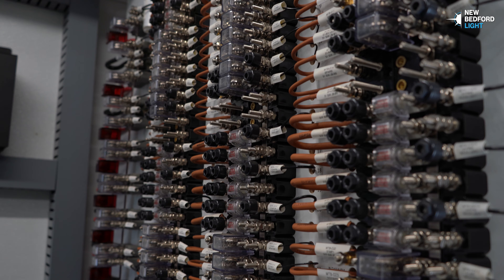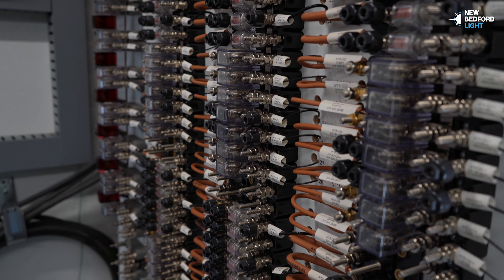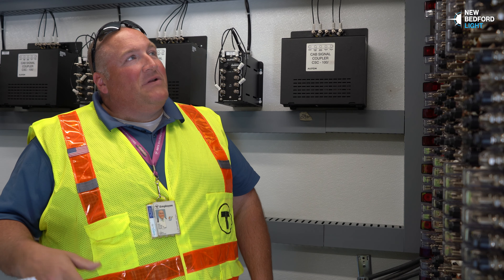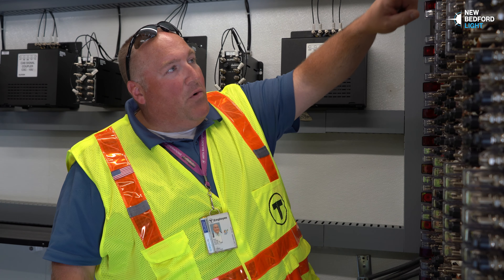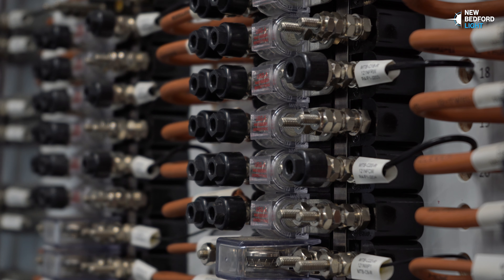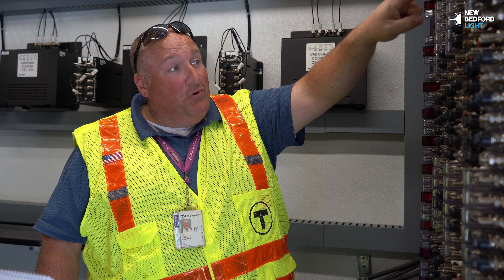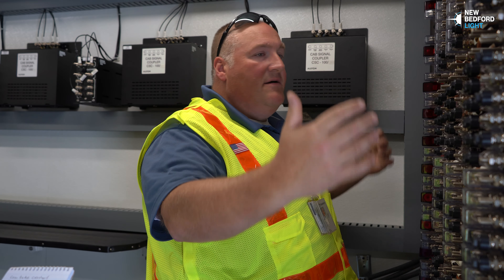These, just like a surge protector in your house, prevent the big damage from occurring to all of this. So after a lightning storm in this area, I'd expect to walk in and find this whole row blown out. When they get blown out, that lightning bolt comes through these wires and explodes these versus exploding the main equipment. We replace them, put new ones in, and we go back to business.